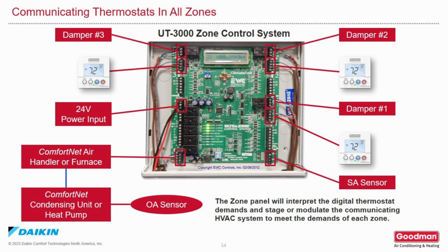Here's an example of the zone control system layout using communicating thermostats. When communicating thermostats are used on all zones, the zone panel will interpret the communicating thermostat demand and stage or modulate the HVAC system to meet the demands of each zone.